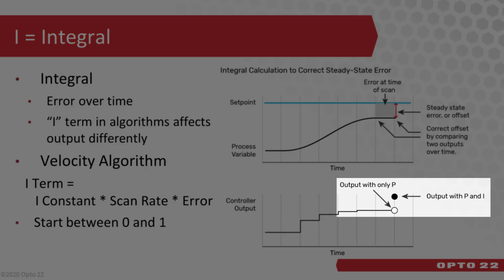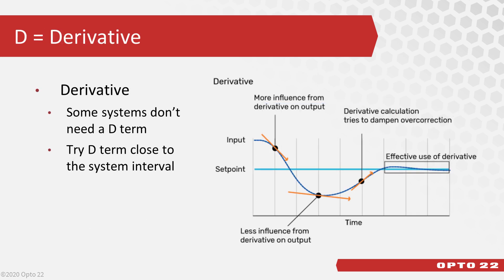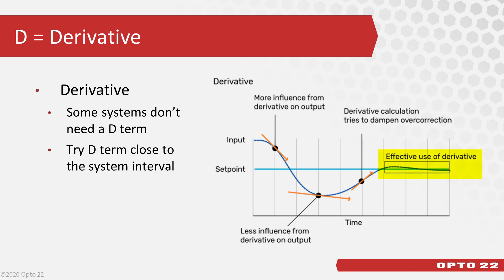How the I term affects the output depends on the algorithm used. For the velocity algorithm, the I constant is the value you'll set — for starters, choose a value between 0 and 1. Many times, using the P and I terms alone is sufficient. But some systems can overshoot the setpoint, causing too much over and under correction. In the real world, this can lead to excessive wear on equipment. The D term, or derivative, is based on the rate of change, or slope, of the process variable. This slope coincides with the speed that the process variable is either approaching or departing from the setpoint. The D term adjusts how much it affects the output, letting you add bigger proportional and integral values for a faster response and better performance while keeping the loop stable.